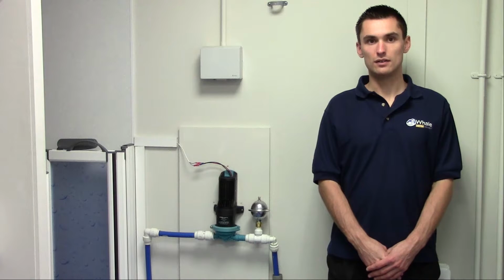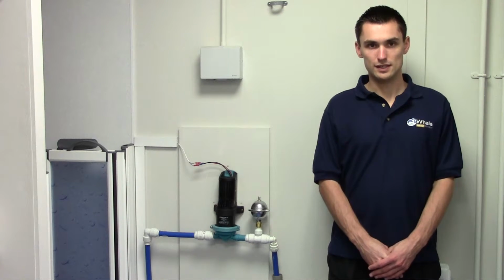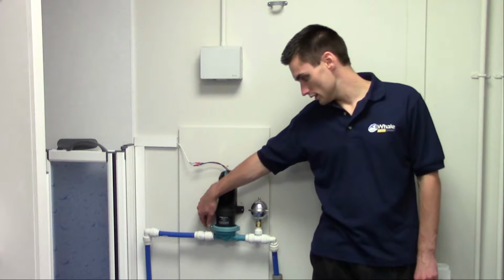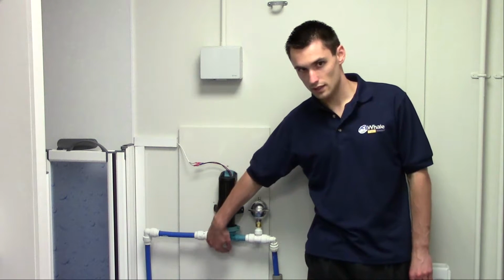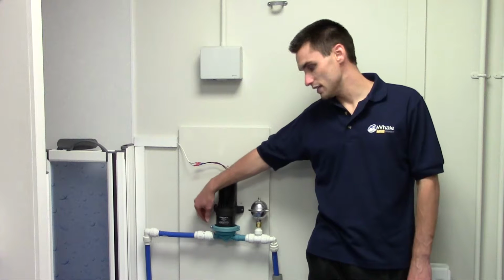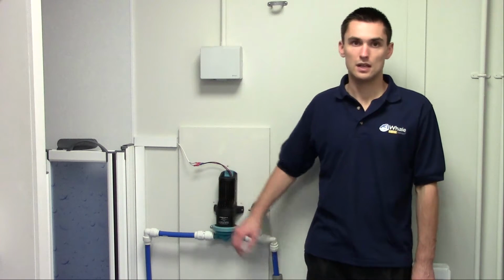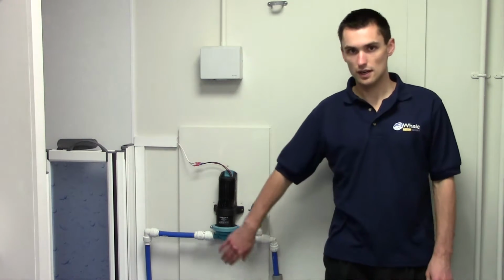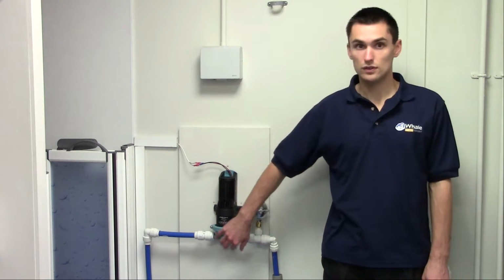It is important to install the pump with the head facing down. Mount the pump on a solid wall or off a bracket on the floor. Vibration on a stud wall will cause noise. Depending on the installation, the pump head can be rotated simply by loosening this screw, rotating the pump head and retightening this screw again. It is important that the flow of water goes in the direction of this arrow found on the head of the pump.